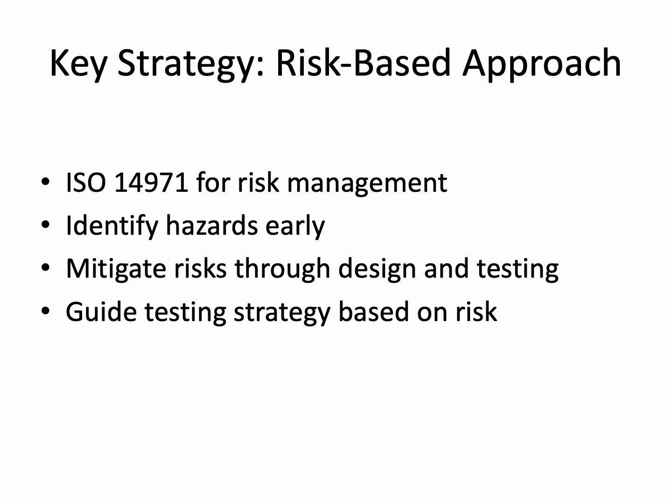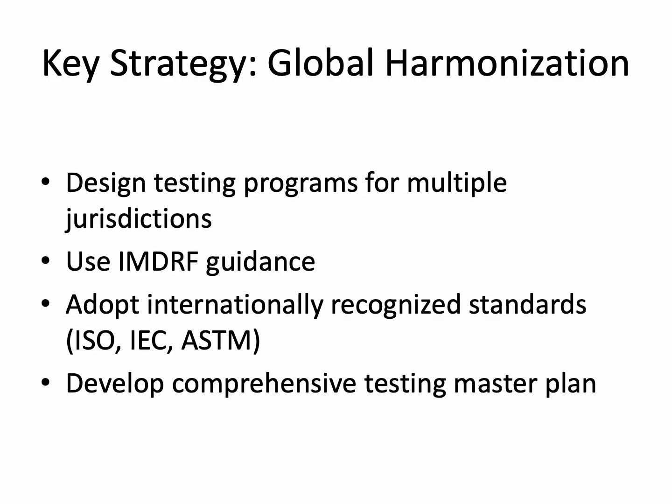A risk-based approach is essential for demonstrating safety and efficacy. Implementing ISO 14971 standards ensures structured identification, assessment, and mitigation of hazards. Risks are addressed through design, testing, and monitoring strategies. Risk assessment informs the scope and intensity of bench, preclinical, and clinical testing, ensuring that regulatory evidence is proportional to device risk. Global harmonization ensures that testing programs satisfy multiple regulatory authorities.